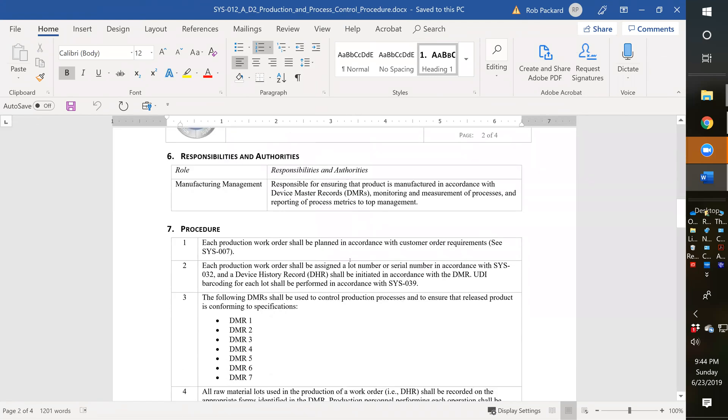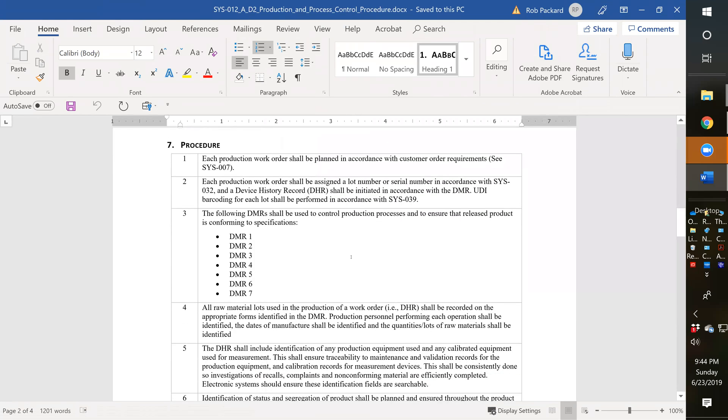As you go through the procedure, you'll notice a section where we listed a bunch of DMRs. Your DMRs can have any numbering scheme you want, and they could be technical files instead of DMRs. The point is the details of each product and how to build it aren't going to be in this one procedure - it makes it too burdensome and detailed. You're presumably going to have more than one product in the future, so it would become extremely hard to maintain.